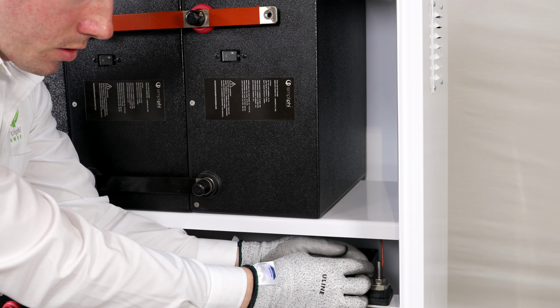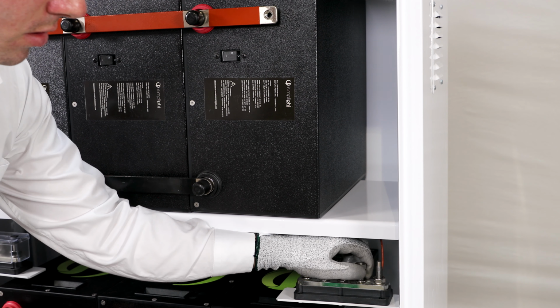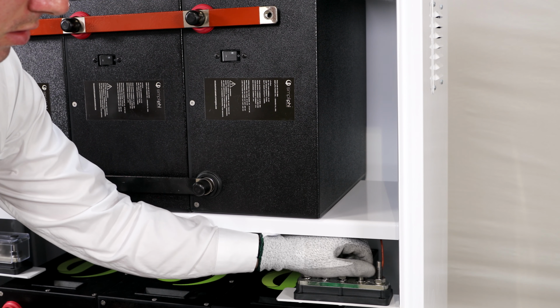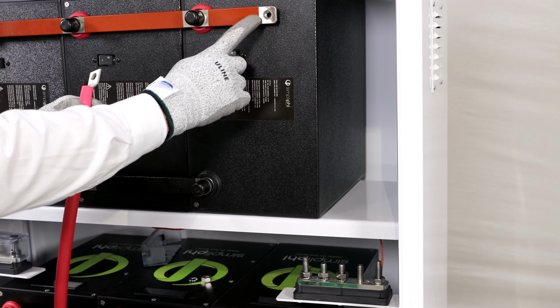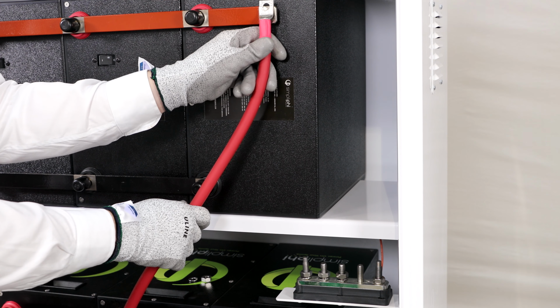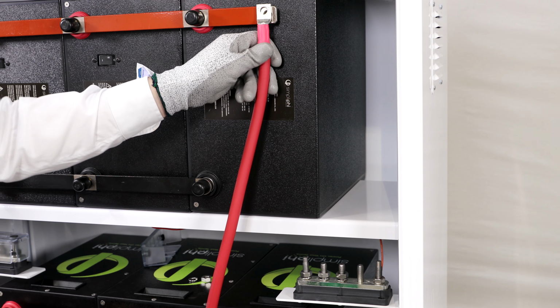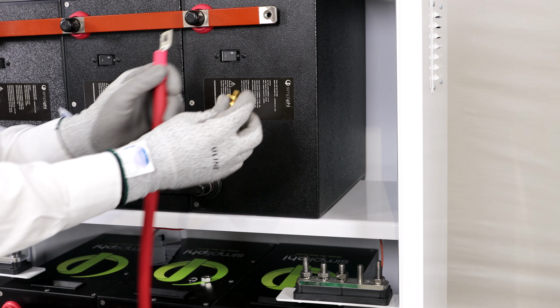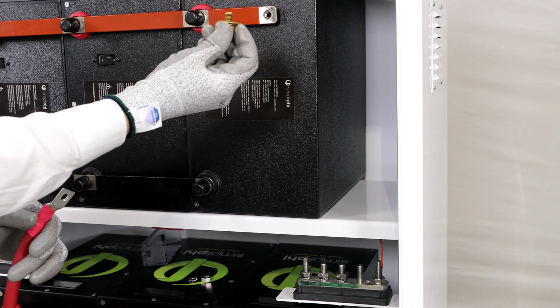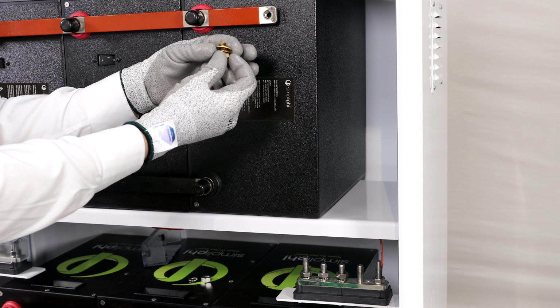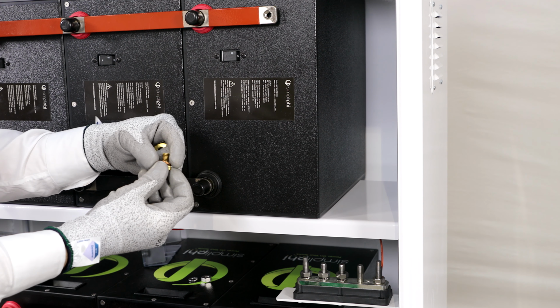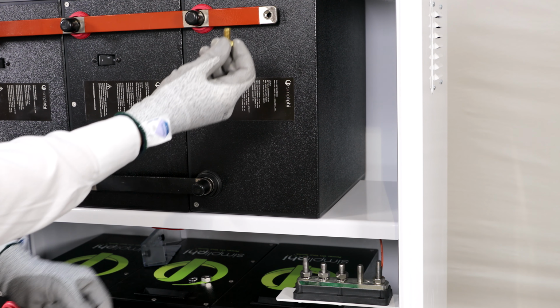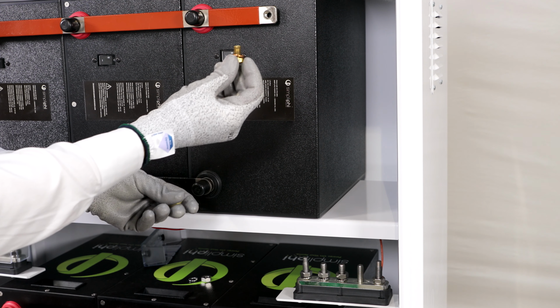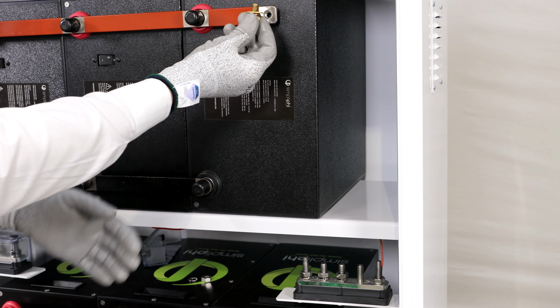We will be landing the top shelf positive bus bar to the terminal block post second in from the right. Connect 2-aught cable to the bus bar using the included 3/8-inch brass hex head cap screw. When connecting the brass hex head cap screw, ensure the lock washer is placed over the screw's threading first, followed by the flat brass washer.